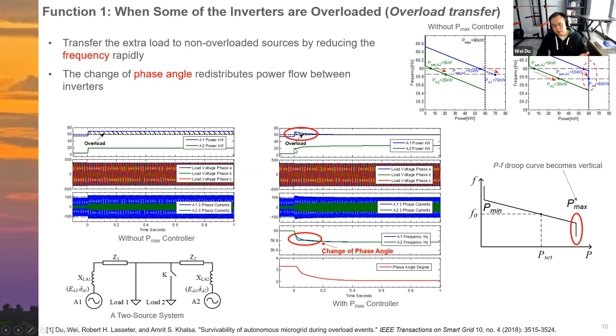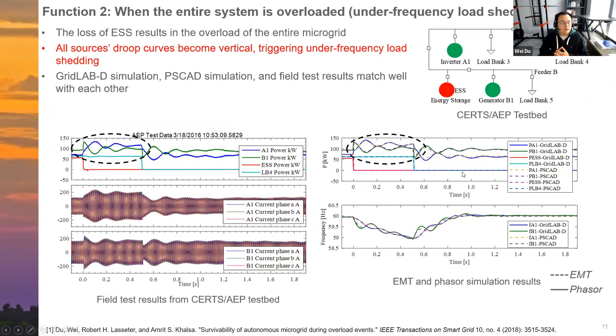So you can see that after about 0.2 seconds, the output power of A1 stays at its maximum, and the second source just picks up the extra load. So this is just an autonomous load transfer from A1 to A2 using this Pmax controller. After talking about the first function, overload transfer, here we'll talk about the second function. It is a more severe case in a microgrid, because sometimes a loss of generation units in the microgrid can result in the overload of the entire microgrid. So how to let the microgrid survive these severe overload events is the second challenge we need to deal with.